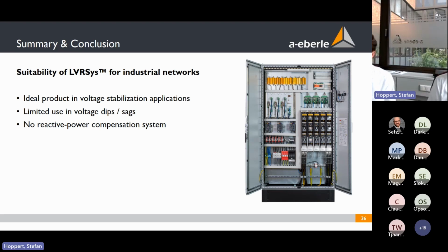Yes. So it's the topic. We do not have a higher THD level. The reason is we are not using the thyristors as an inverter. As Thomas mentioned, we are using the thyristors like a mechanical contactor to switch on and off. If the thyristors are fired on, they are not switched at a frequency of 10 or 20 kilohertz or something. It's just to be switched on. And if you're generating the next step, we will switch the next thyristors on.